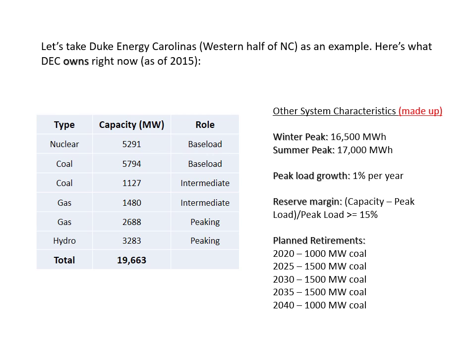Peak load growth's about 1% per year. That's a rule of thumb for a lot of places in the United States, although some are less, some are slightly more. They have to build in some system redundancy, right? And we've talked about how you do that and the metrics for doing that. We use this term, the reserve margin, which is a measure of how much capacity they have left over after they're dealing with peak demand.